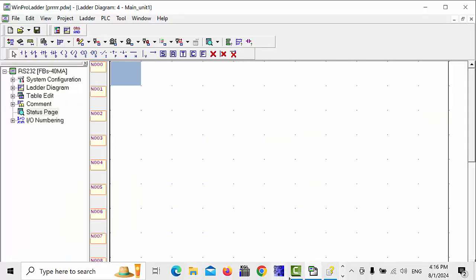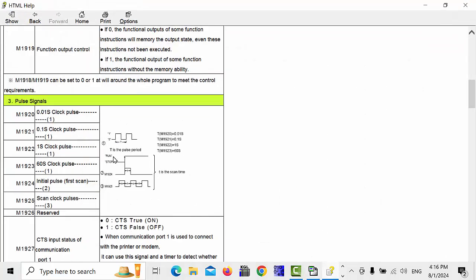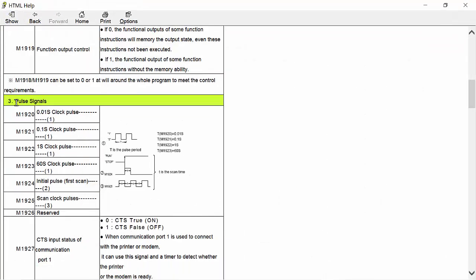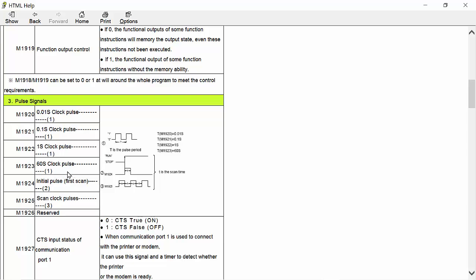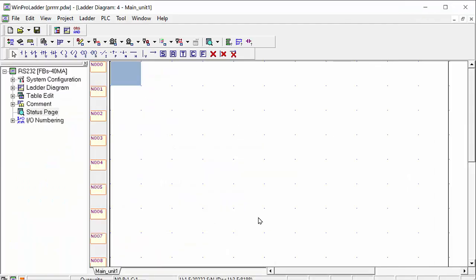First of all, I will introduce you this is the manual of our Fatek PLC. There is he saying pulse signals. In chapter number 3, he says M1920 is a 0.01 second clock pulse. One available. And also one more M1921 is a 0.1 second clock pulse. And M1922 is a 1 second clock pulse. And M1923 is a 60 second clock pulse. And how we can use in these relays, I will show you in the program.